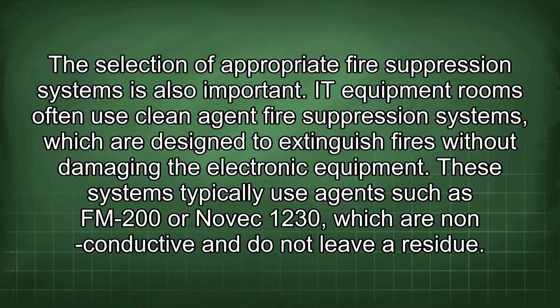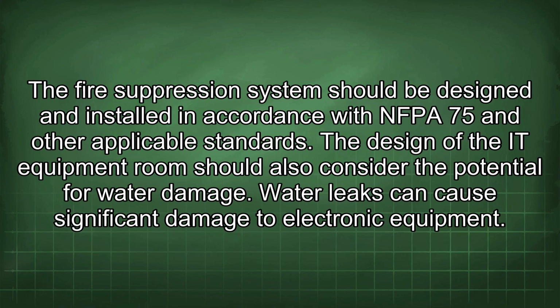The selection of appropriate fire suppression systems is also important. IT equipment rooms often use clean agent fire suppression systems, which are designed to extinguish fires without damaging the electronic equipment. These systems typically use agents such as FM-200 or Novec 1230, which are non-conductive and do not leave a residue. Fire suppression systems should be designed and installed in accordance with NFPA 75 and other applicable standards.